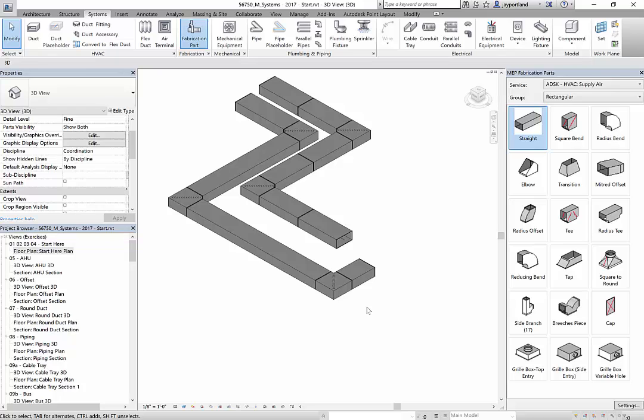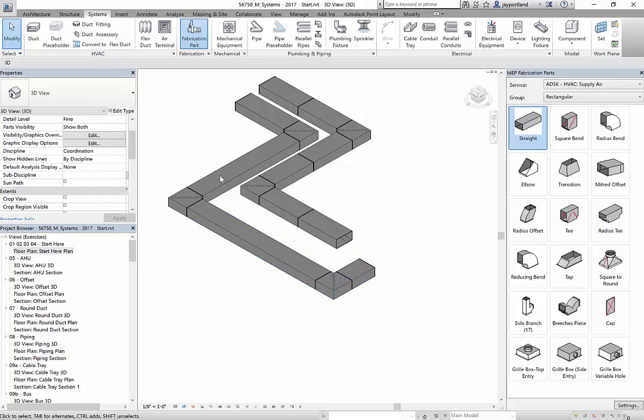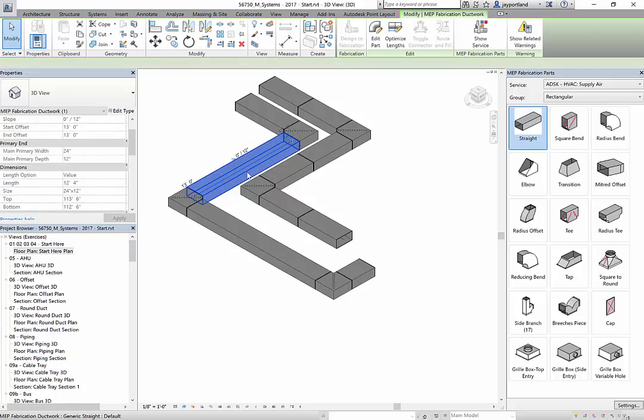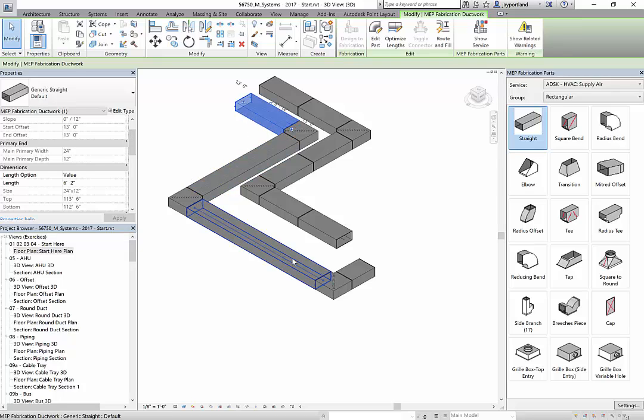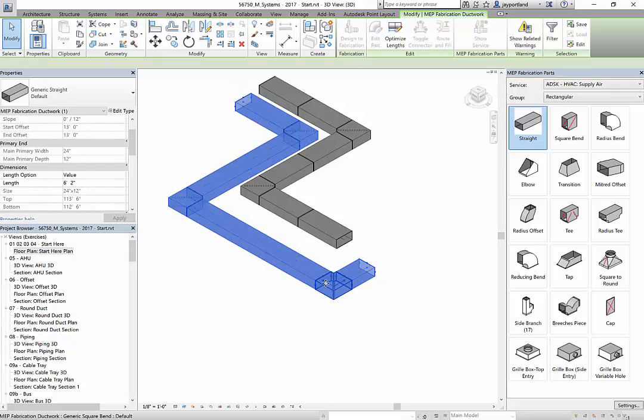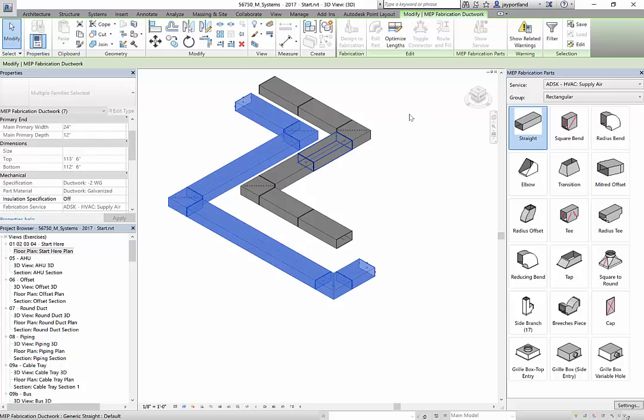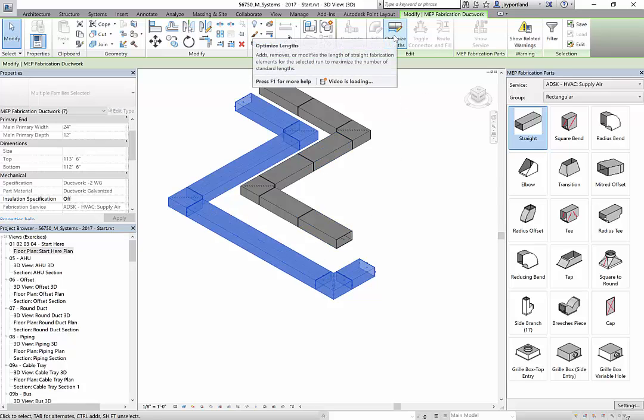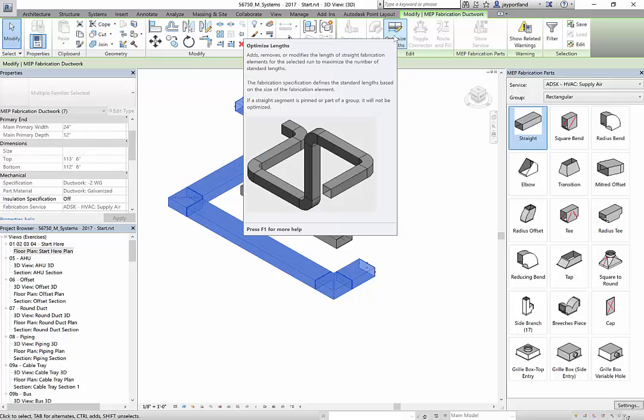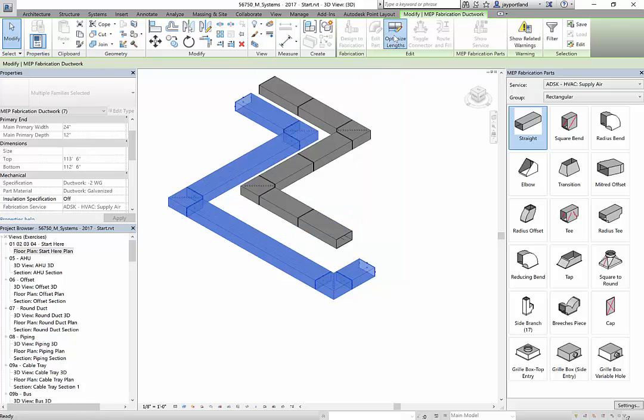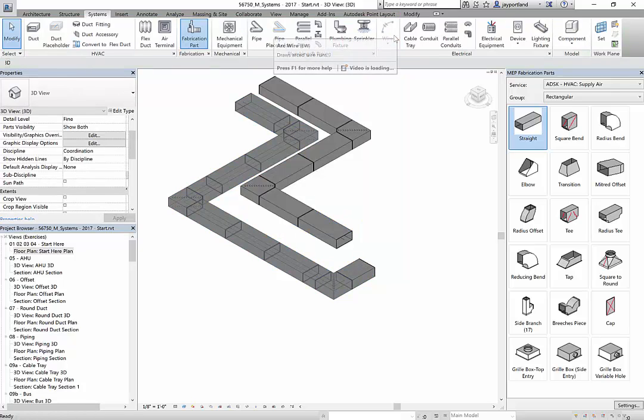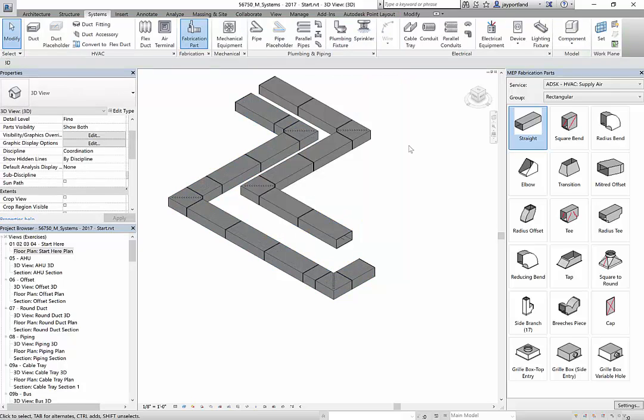Now, we're not quite done yet because as you can see, we've got these long lengths of ductwork that are not the standard length. If I look at the length here, you'll see that it's 12 feet 4 inches. So what I would do in this case is select the run of piping and then hit the optimize length button. It's in the contextual ribbon. Once you select it, it'll divide all of those components up to the standard widths, the standard lengths that you have defined for your service.